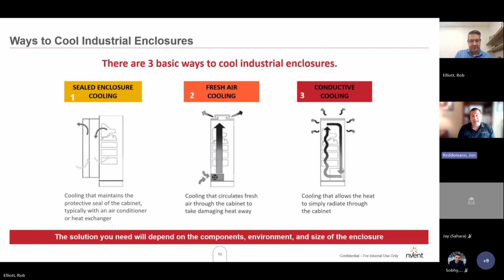That's a great point. That actually is the worst thing that we can do in this scenario, is put the largest system on that we can. Because ultimately what happens is, we have a heat load in a fixed space, and if we put too big of a cooling system on there, too big of an air conditioner, we will promote short cycling within that air conditioner. And we will start to burn through the life cycles of the components within the air conditioner.